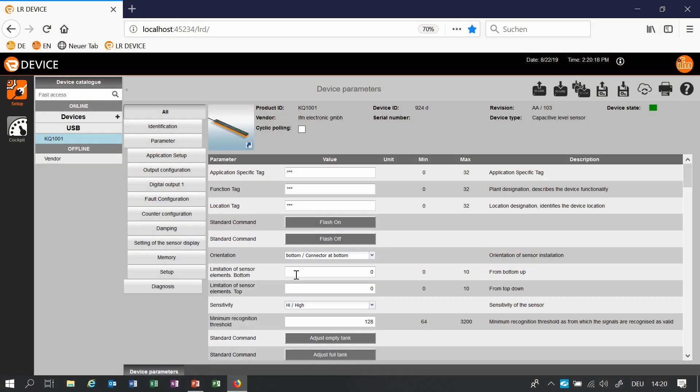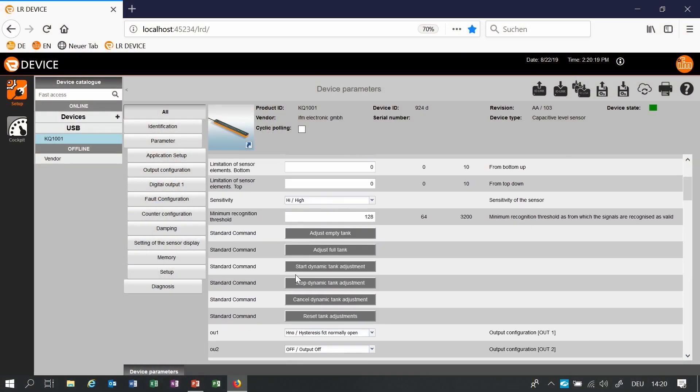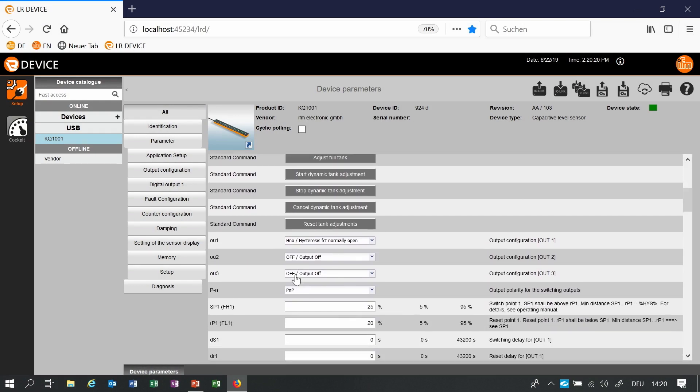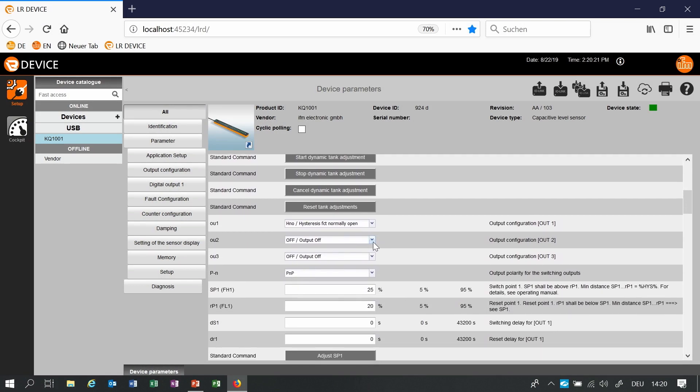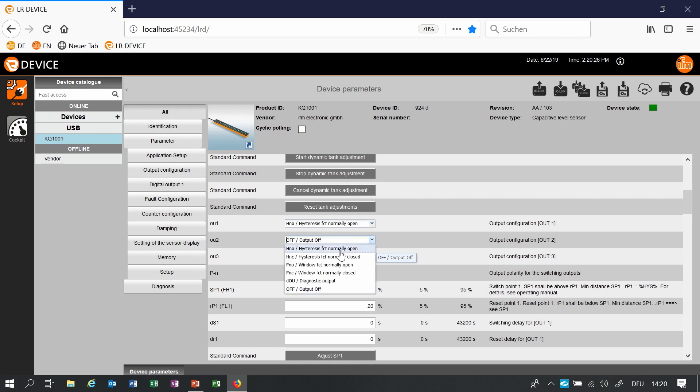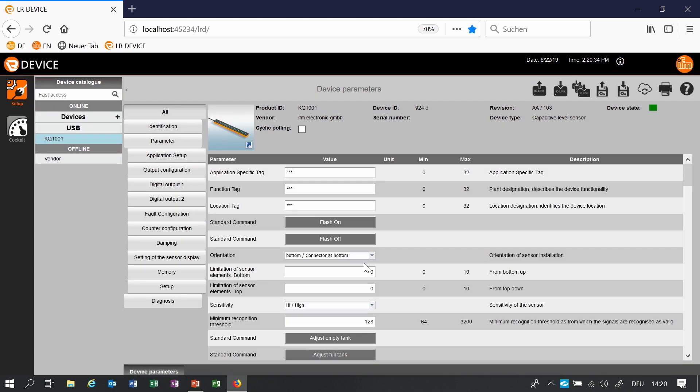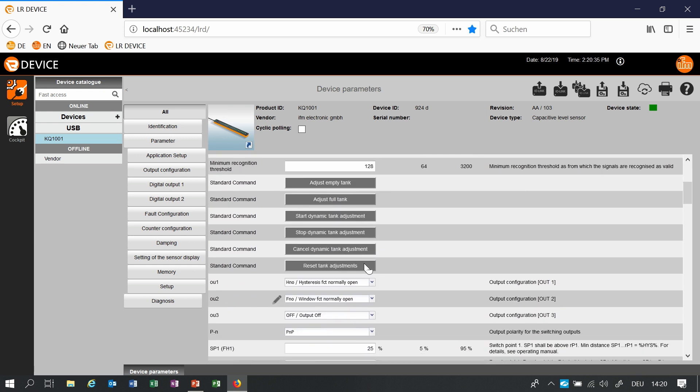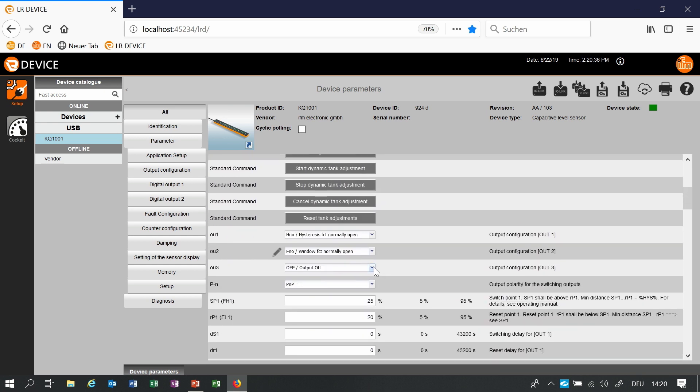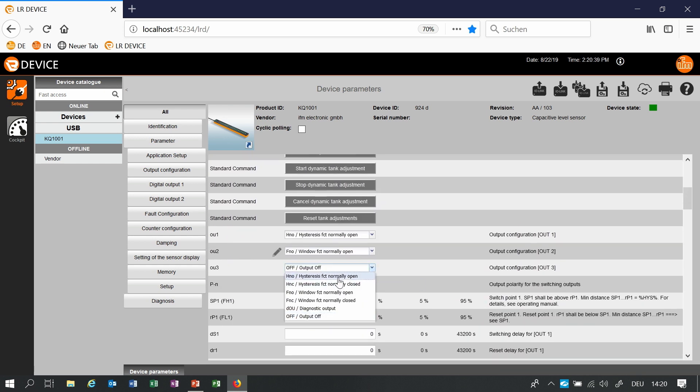As I said before the sensor has three switch points via cable. Factory setting is that just one switch point is available so if you want to use the additional two you have to set it. In this case I will use for example the function window function normally open for the second switch point and I will choose also a hysteresis function for the third.